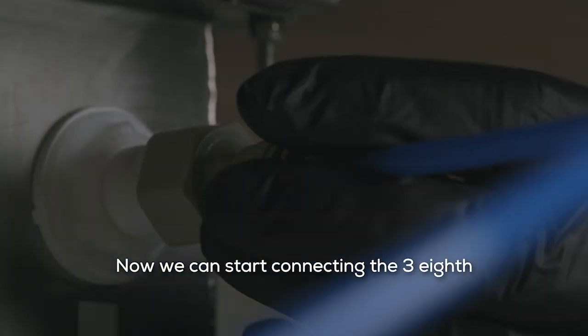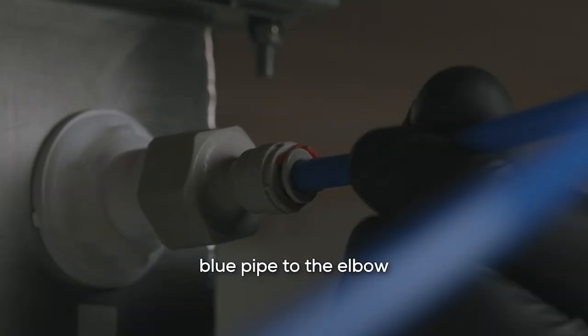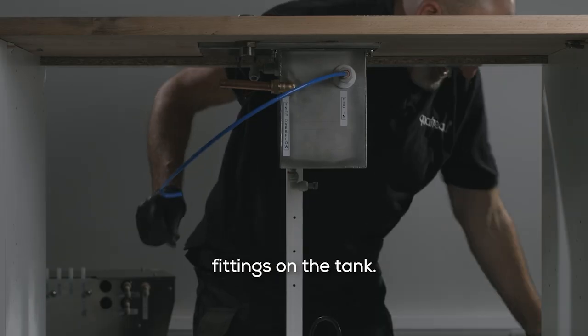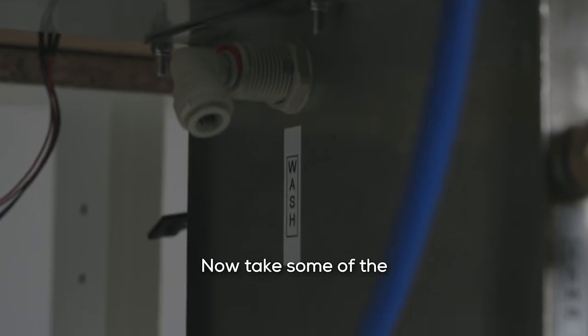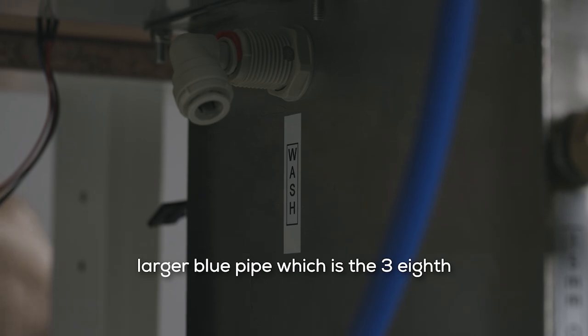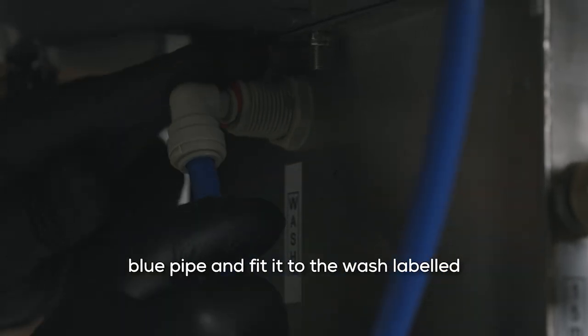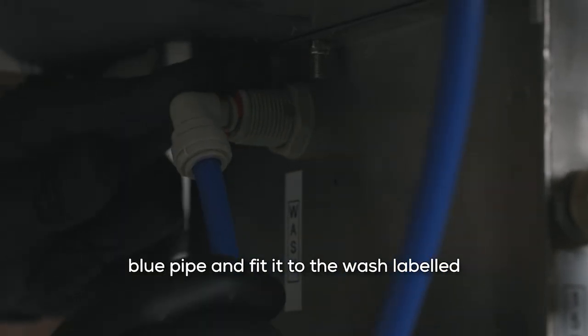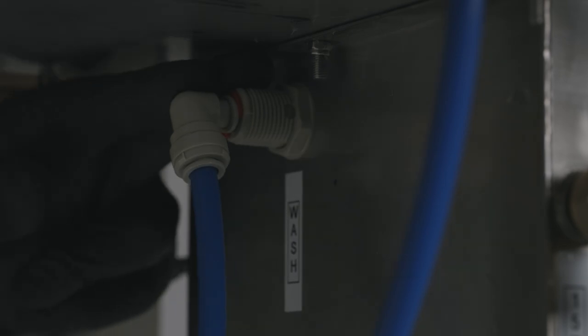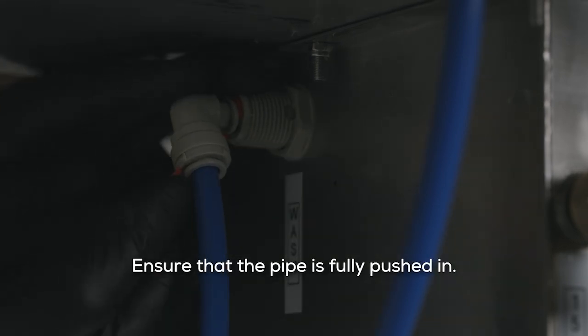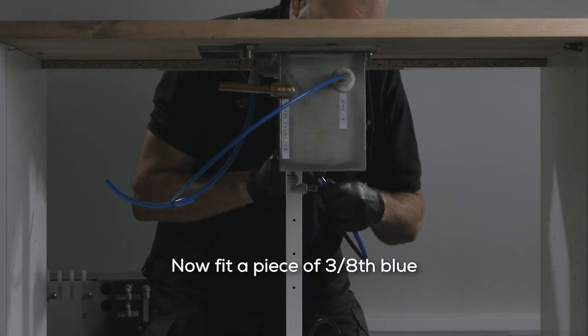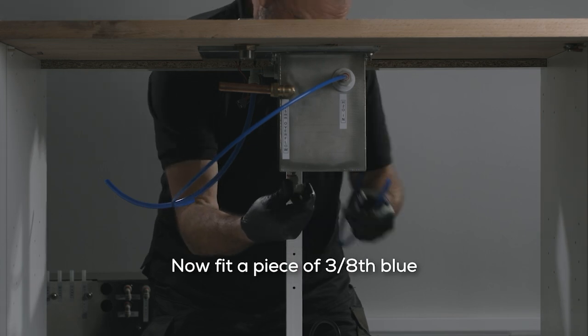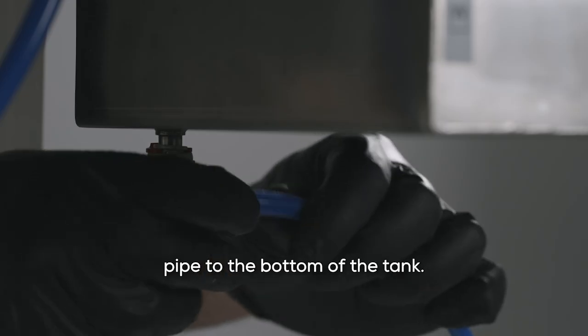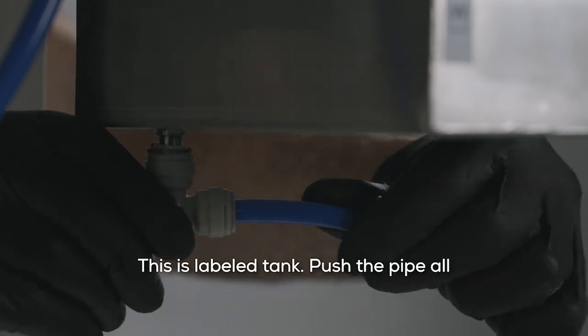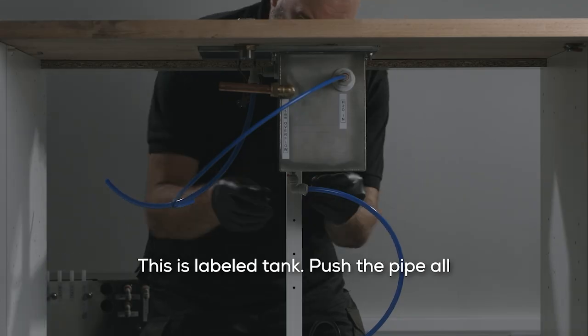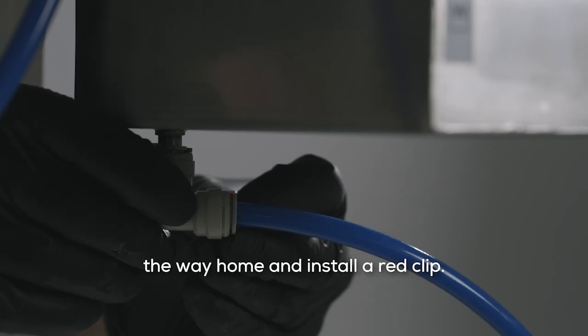Now we can start connecting the 3/8 blue pipe to the elbow fittings on the tank. Now take some of the larger blue pipe, which is the 3/8 blue pipe, and fit it to the wash labelled fitting on the side of the tank, ensuring that the pipe is fully pushed in. Now fit a piece of 3/8 blue pipe to the bottom of the tank. This is labelled tank. Push the pipe all the way home and install a red clip.